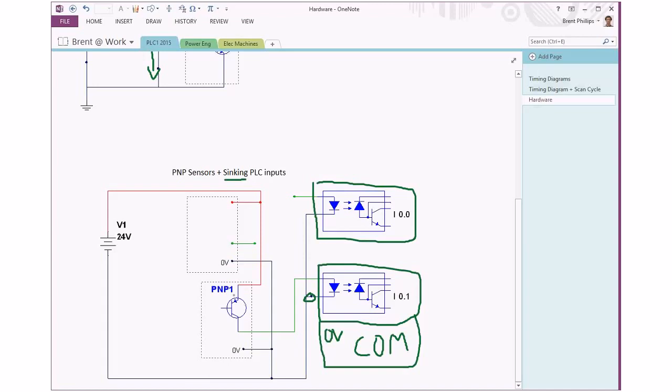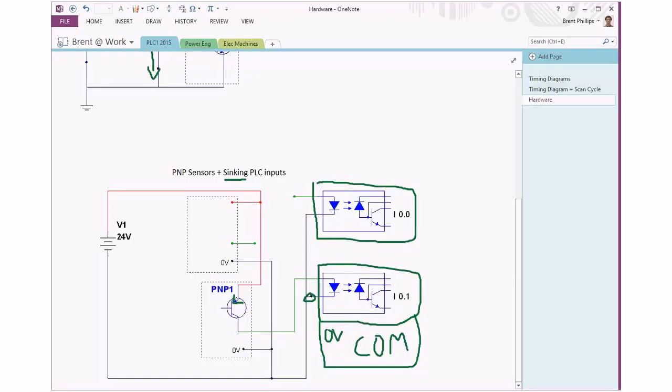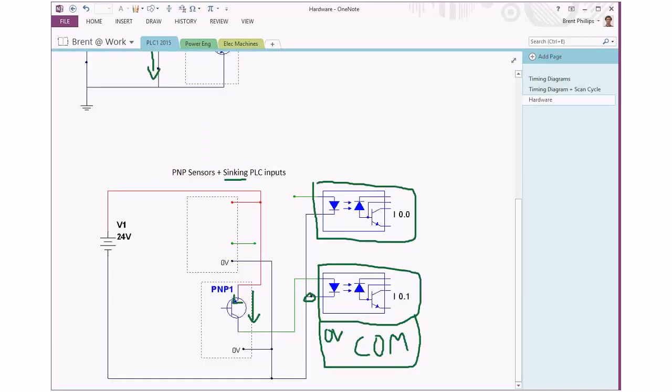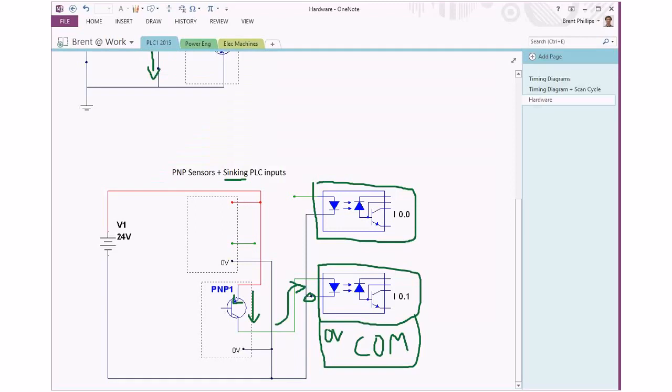We've got a PNP transistor where the arrow points into the transistor - that's our current flow direction. We still have current flowing through our sensor and flowing up and into our PLC. It's going to activate the PLC circuit, and the connections are just slightly different. These are all based on three-wire type sensors.